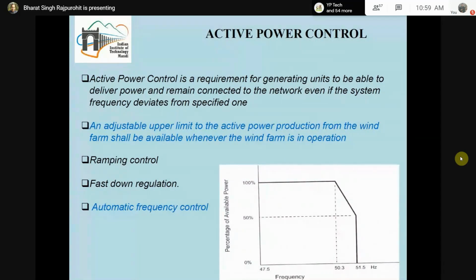The second requirement, which people are talking about now and which may be implemented, is that instead of operating at the maximum power point, the wind farm should be able to set its active power output, let's say 10% below this. So for a given wind speed, if 100 units of electricity can be generated from a wind energy conversion system, the set point is set at 90 units. It means we are continuously wasting 10 units of electricity.